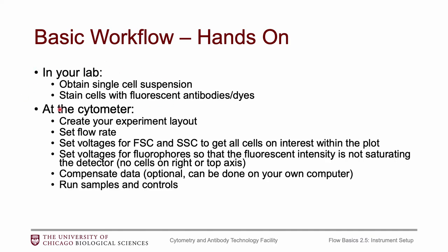The workflow for the hands-on component of your experiment: you'll start in your lab, get a single cell suspension, and stain your cells — that's what we covered in the first two videos. Then you'll come to the flow core and at the cytometer you'll need to create your experiment layout, decide on flow rate, set the voltages for forward and side scatter as well as the fluorophores, and decide whether to compensate on the instrument or in analysis software. Once set up, you run your samples and controls, then analyze your data with FlowJo, FCS Express, or whichever application you prefer.